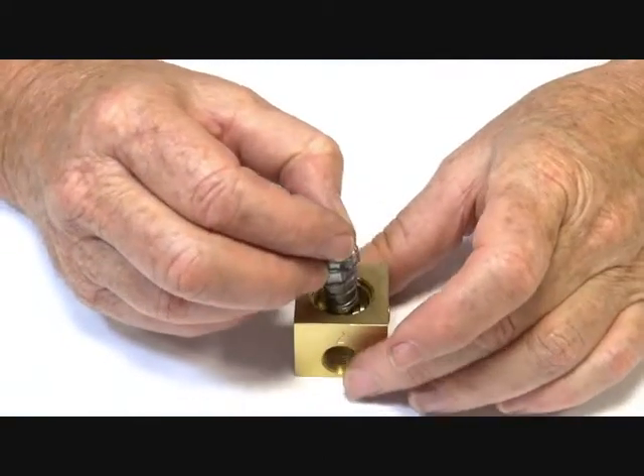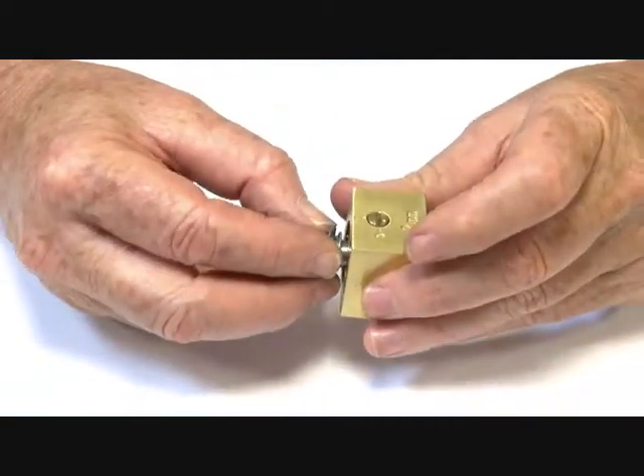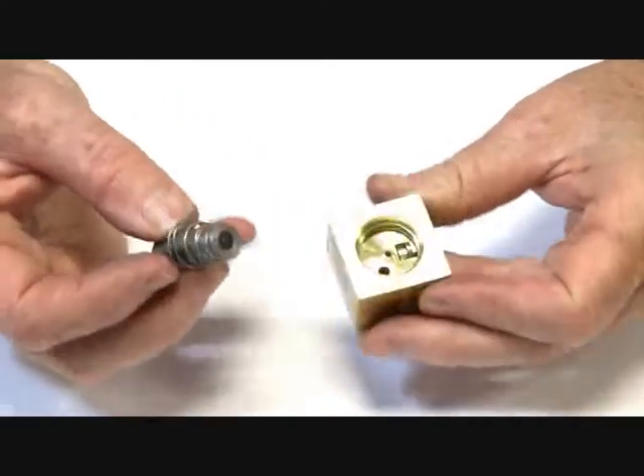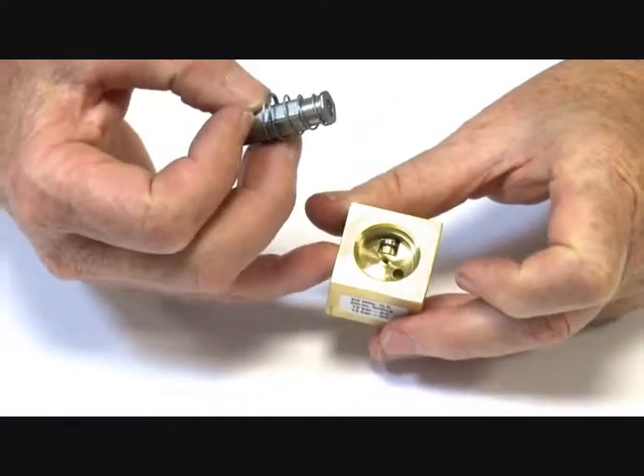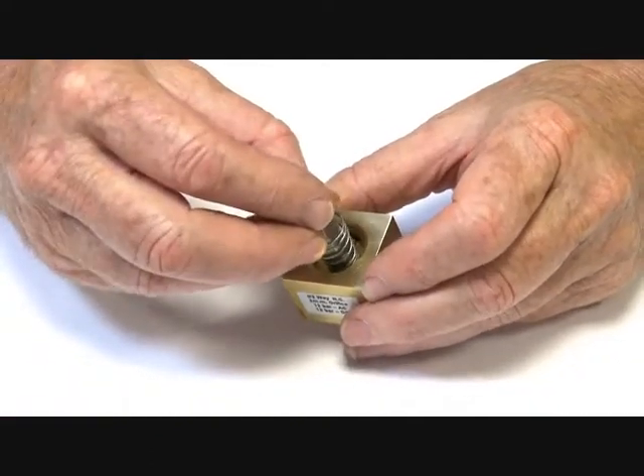So in the normal function, de-energised, this armature assembly is sitting down here with the spring. The media is coming in through port 1 and sitting underneath that jet, which is underneath this little seat, sealing off like that.